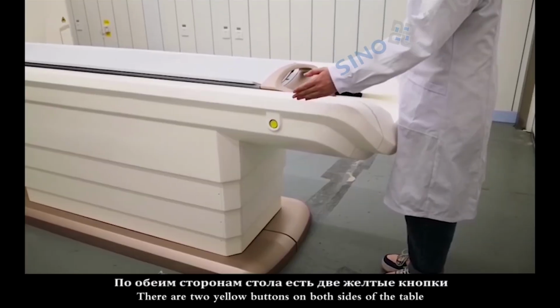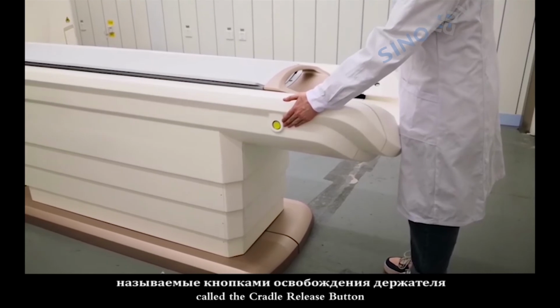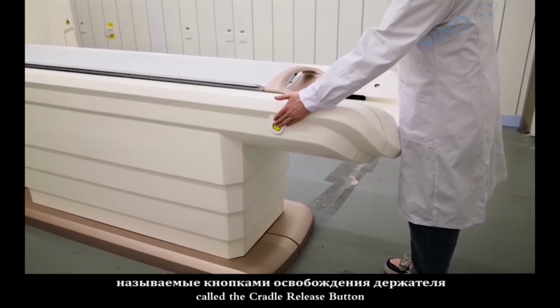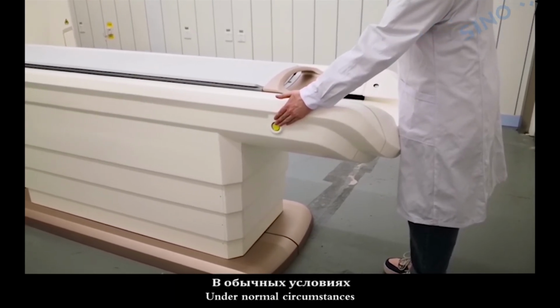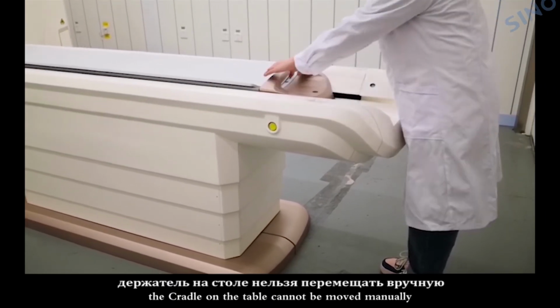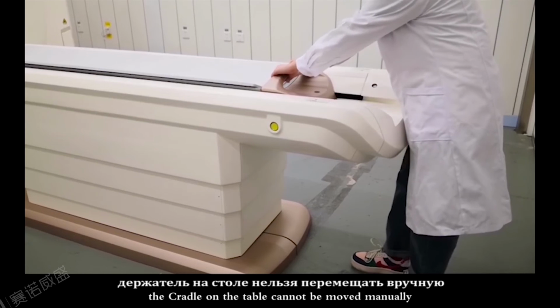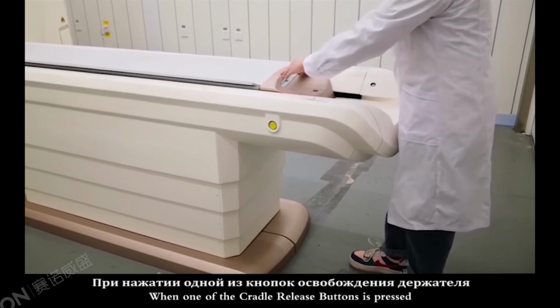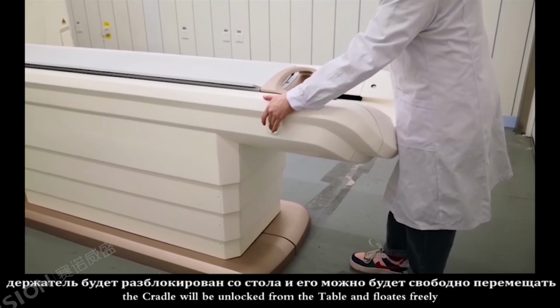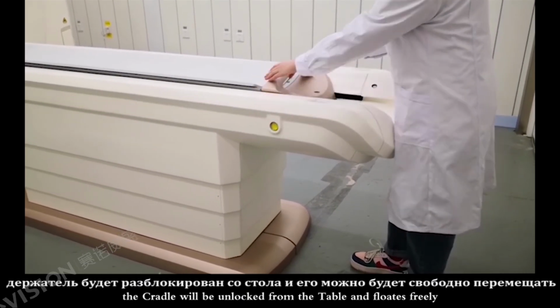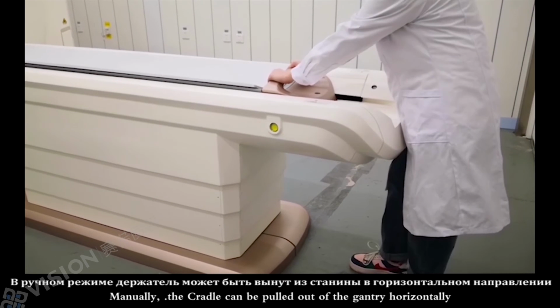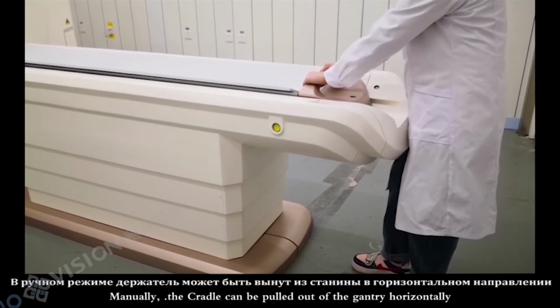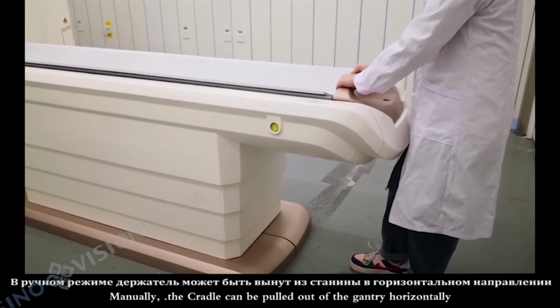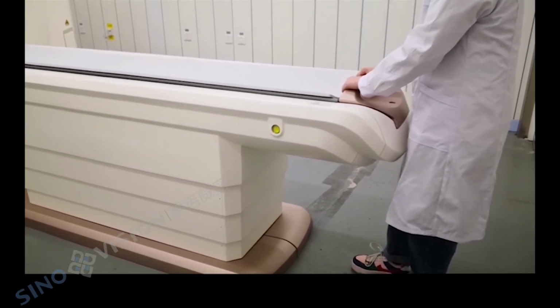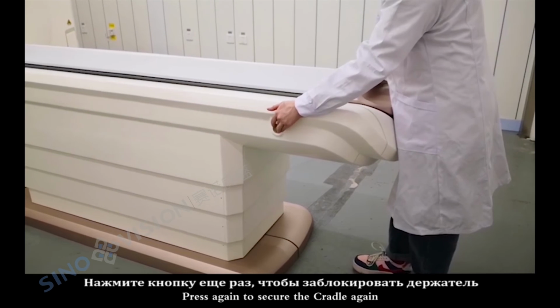There are two yellow buttons on both sides of the table, called the cradle release button. Under normal circumstances, the cradle on the table cannot be moved manually. When one of the cradle release buttons is pressed, the cradle will be unlocked from the table and floats freely. Manually, the cradle can be pulled out of the gantry horizontally. Press again to secure the cradle again.